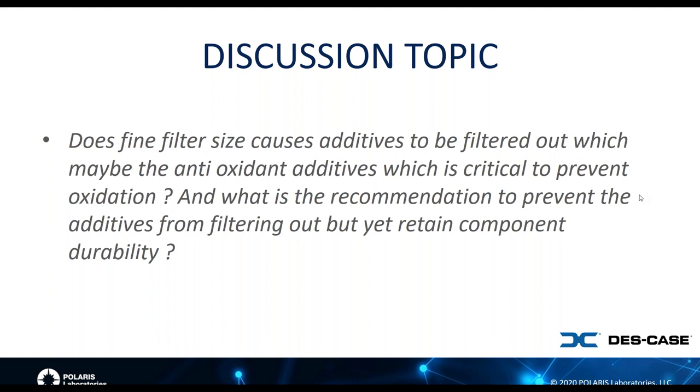Yeah, so that's a very common question that we get around the world of filtration. So the answer to whether you can filter out additives is it depends, and I know that's not an answer that people want to hear, but it really does depend on the type of additive and the type of fluid. So the question specifically mentions antioxidant additives. Antioxidant additives are chemically dissolved within the fluid, whether that's a turbine oil, a gear oil, a hydraulic fluid, or engine oil. So filtering out antioxidant additives is very unlikely. It's almost impossible to filter those out with a mechanical filter.